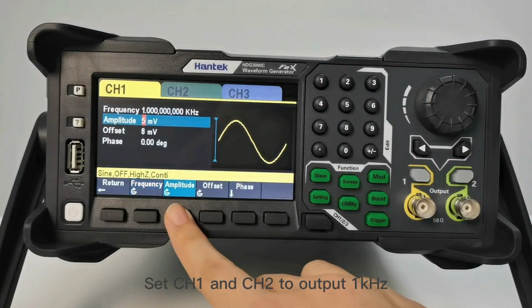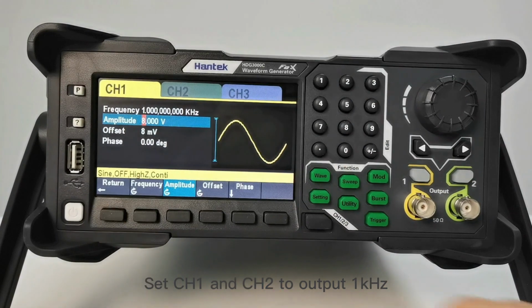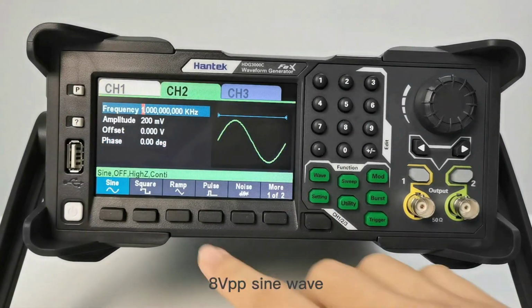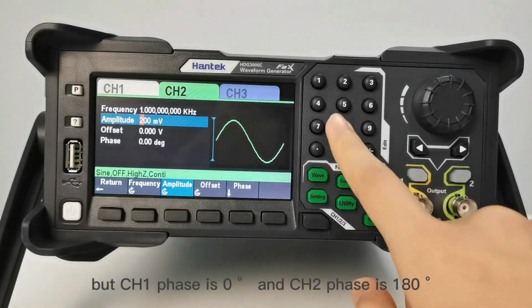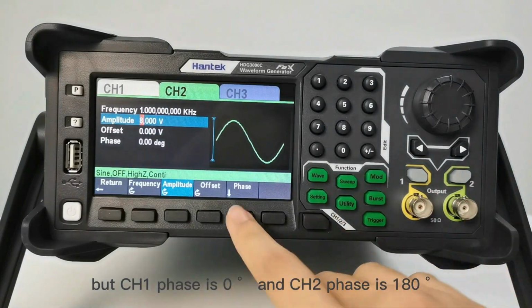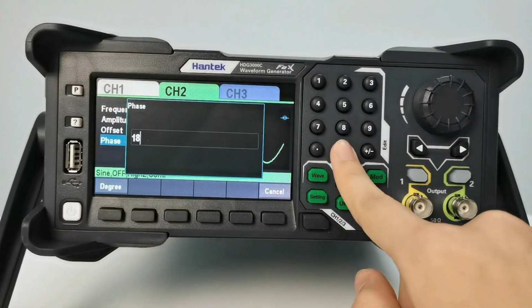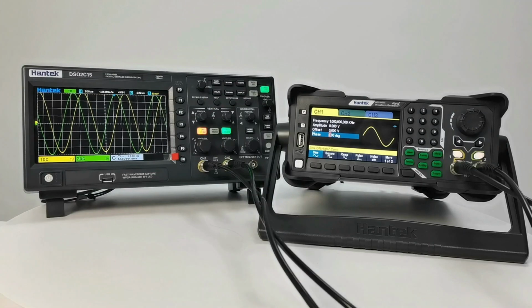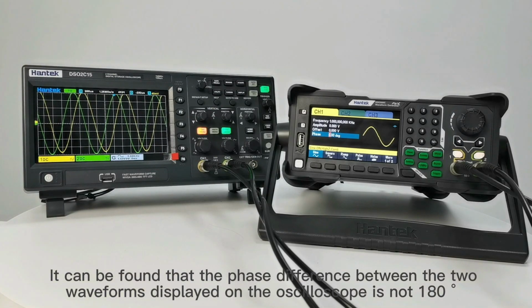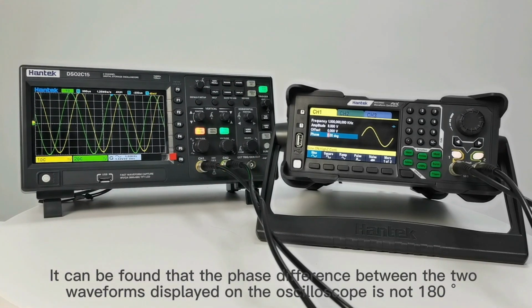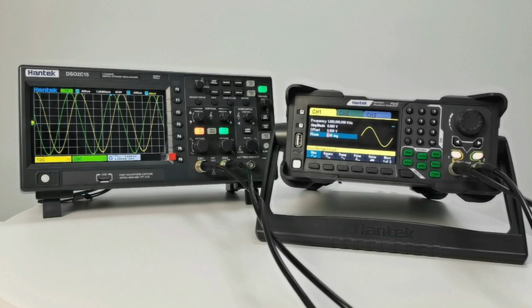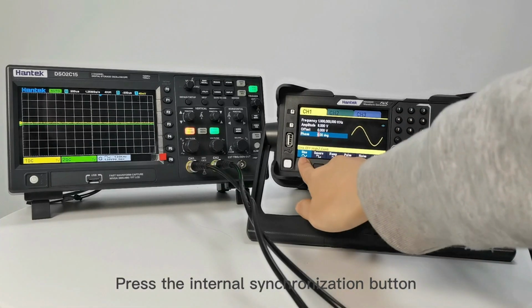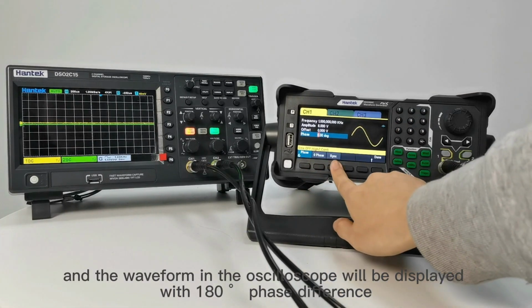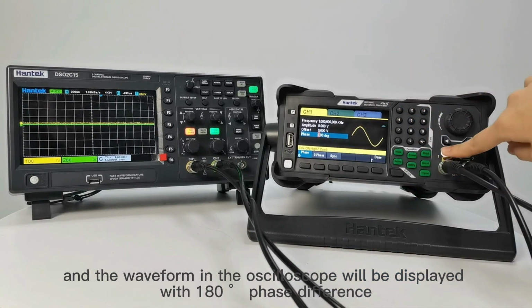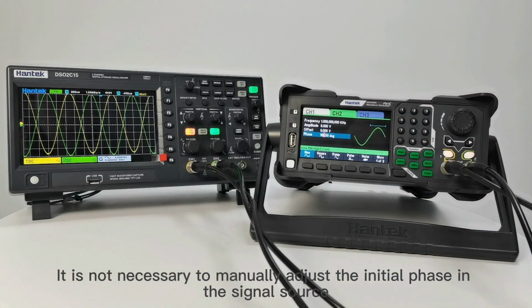Set CH1 and CH2 to output a 1 kHz, 8 VPP sine wave, but the CH1 phase is 0 degrees and the CH2 phase is 180 degrees. It can be found that the phase difference between the two waveforms displayed on the oscilloscope is not 180 degrees. Press the internal synchronization key, and the waveform in the oscilloscope will be displayed as a 180-degree phase difference, without manually adjusting the initial phase in the signal source.